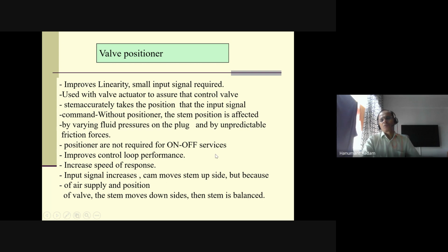Positioners are not required for on-off service. If you require only on and off, a positioner is not required. It improves the control loop performance and increases the speed of response. When the input signal increases, the cam moves the stem upside, but because of air supply and position of the valve, the stem moves downside and the stem is balanced. This slide is not edited, but you can see in it why the control valve positioner is required. It is required because you need a stable, controlled flow rate. If the positioner is not there, your flow rate will be affected by the input side pressure increase of the valve.